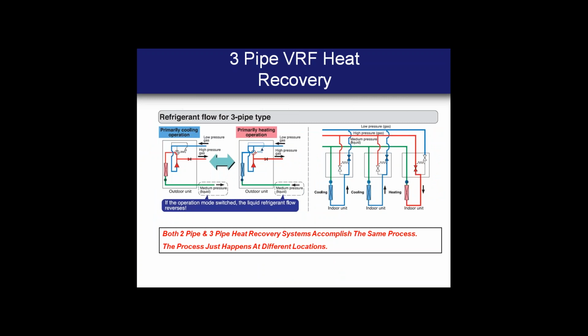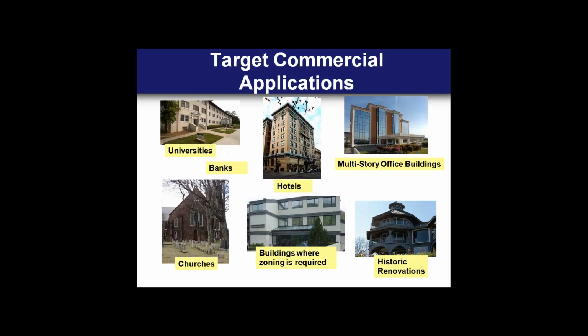So you'll see three individual pipes. Again, those three pipes representing those three different states of refrigerant: low pressure suction gas, a high pressure gas for heat, and a medium pressure liquid. And again, they'll run those three pipes throughout the entire building down to the farthest run, and then branch off of those each time with a branch selector box. Again, that box is only dictating the state of refrigerant to the indoor unit based on the mode it's calling for, and the indoor units would throttle, just as the indoor units in the Mitsubishi system would throttle through their built-in linear expansion valve. So very similar, it's just accomplishing those tasks in different locations.